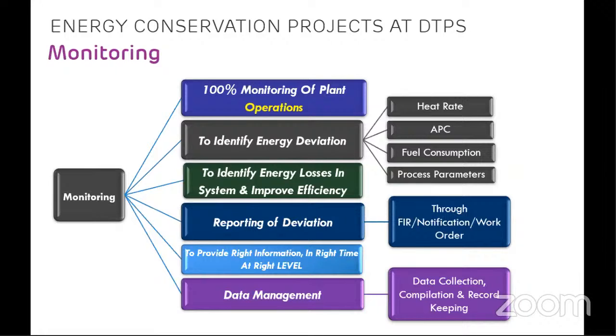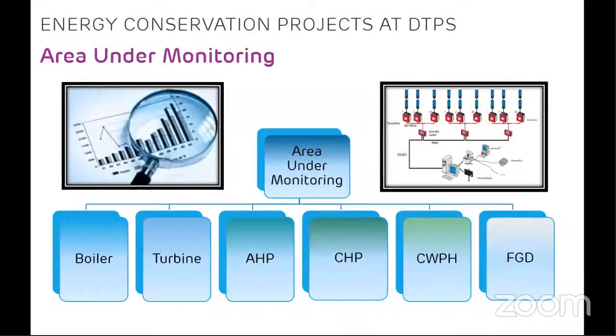And there is a data management system also, which collects data, compiles and keeps records for future reference. Now, the area under monitoring, it is very necessary that we cover the entire plant area. So we are monitoring the entire boiler, turbine, ash handling plant, coal handling plant, cooling water plant and FGD, which is the flue gas desulfurization unit, which we are using in our plant. So this entire plant area is under monitoring.